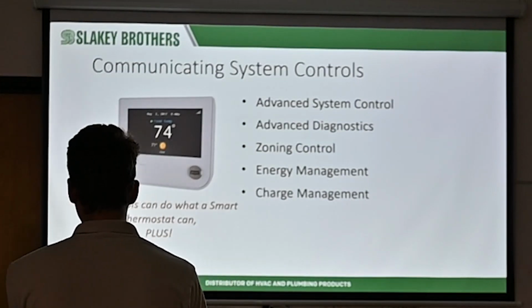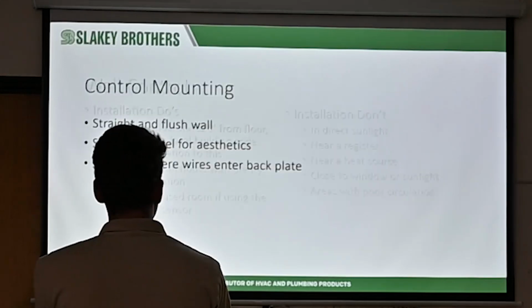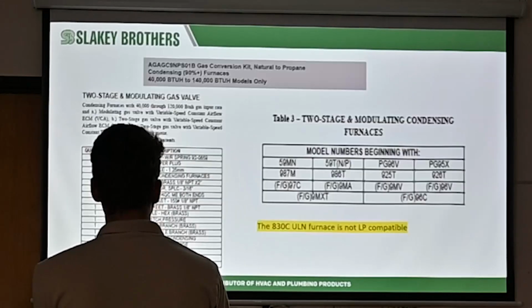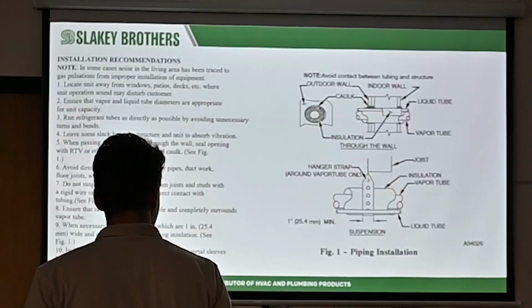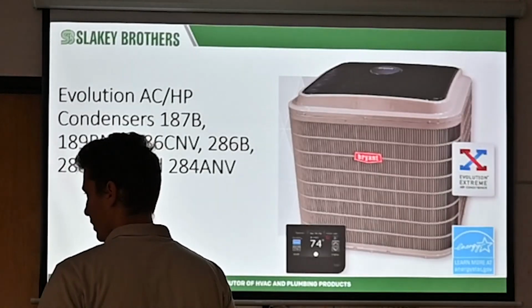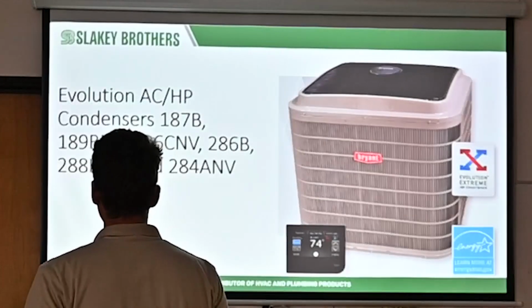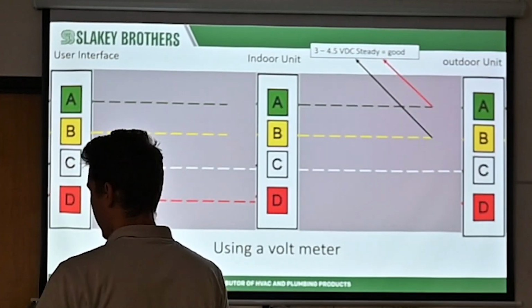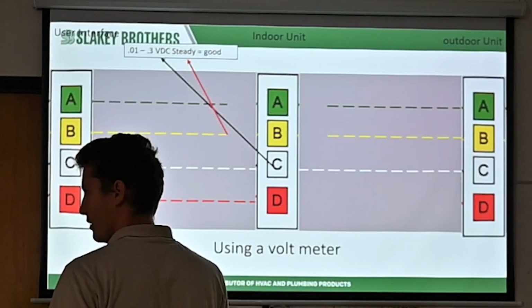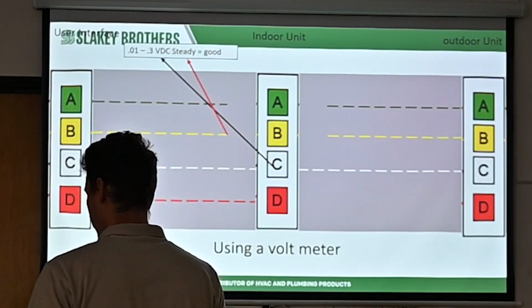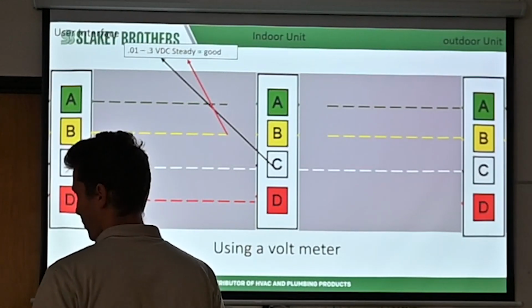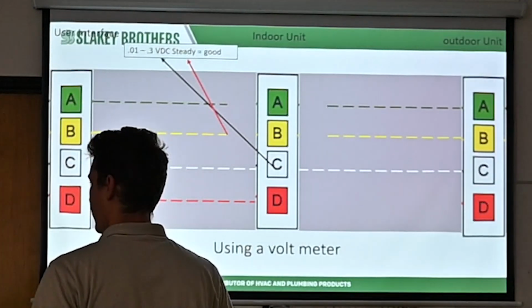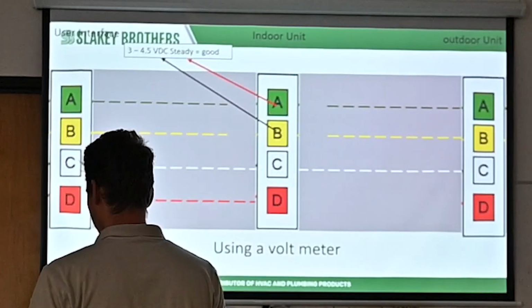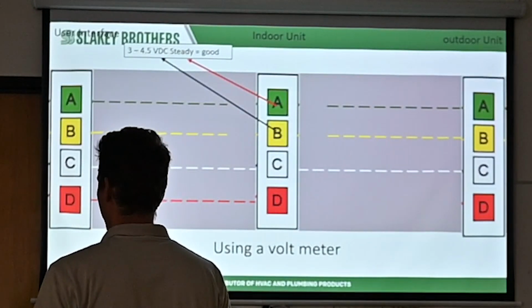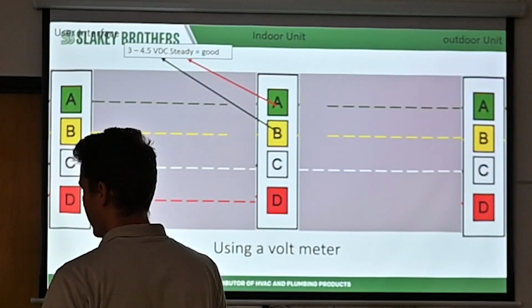You're talking about diagnosing the communication faults. Yeah, and this is the second case. I had a problem. We installed a new system. We tested it for about 4 hours, and everything worked fine. But after that, our electrician came and replaced lights and some outlets. Two weeks later the customer called us and said his system won't work. It works and then stops, works again, stops. I came and checked it, and it was working about 3 minutes, and after that outdoor communication fault, indoor communication fault. Three minutes again, the same problem.